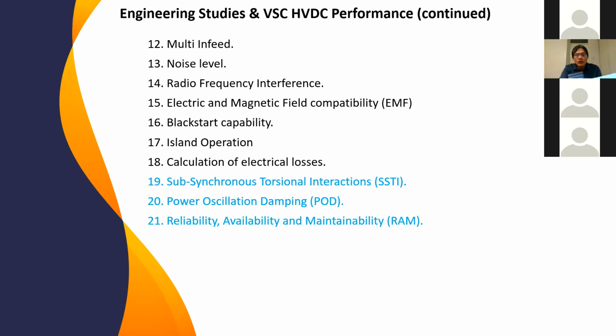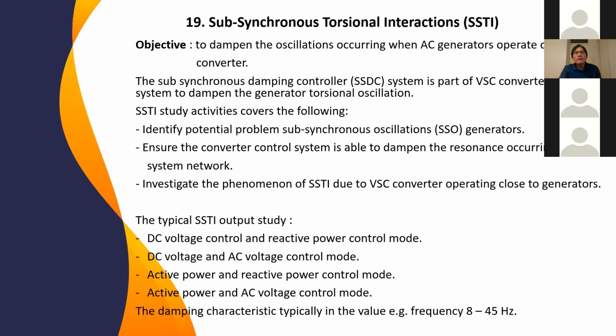Island operation to demonstrate the converter control system has the ability to detect any converter station disconnecting from other converter stations. Calculation of electrical losses to calculate converter station and transmission losses during converter operation. SSTI to dampen oscillation occurring when an AC generator operates close to the converter.